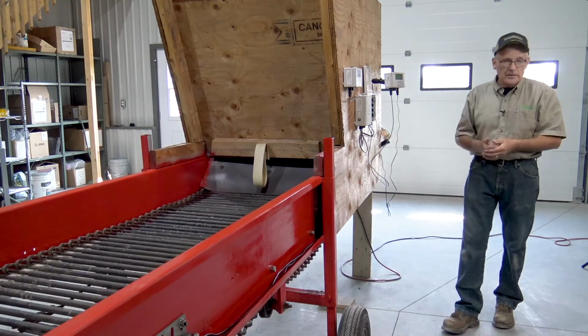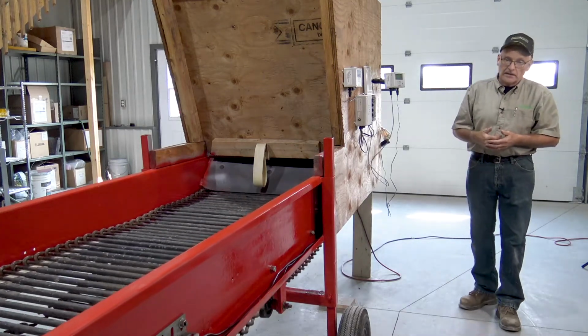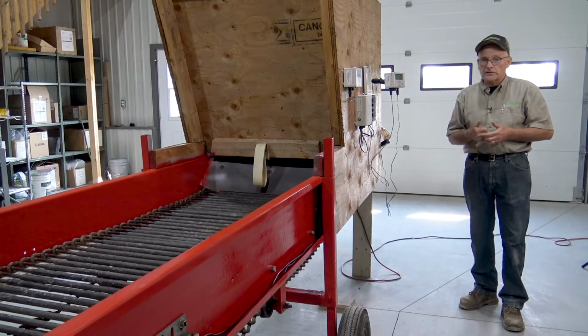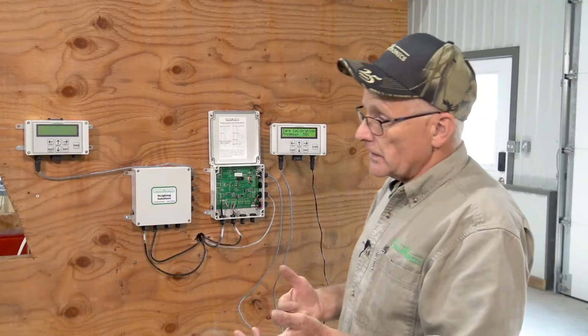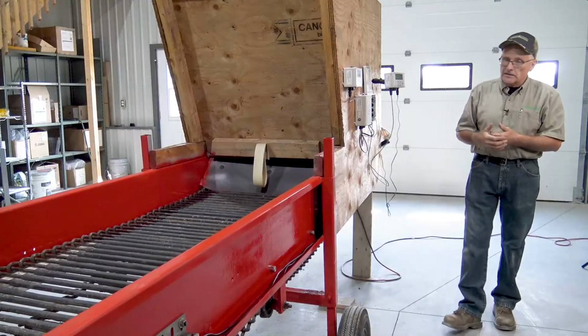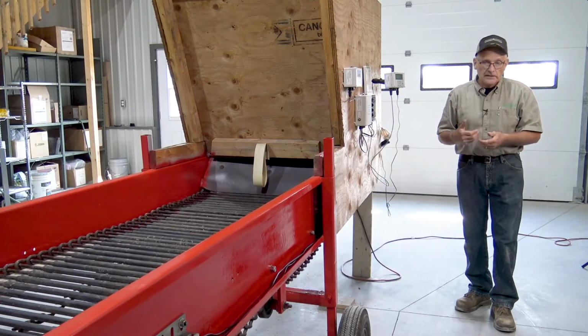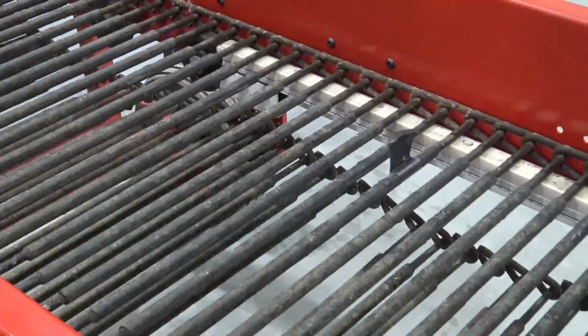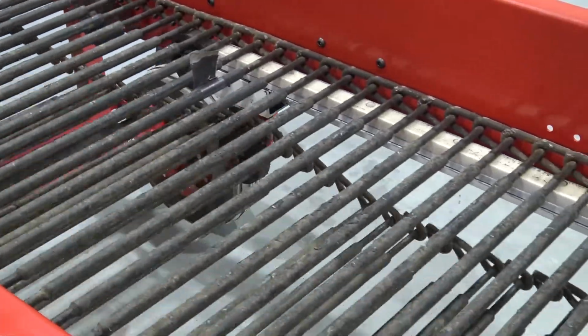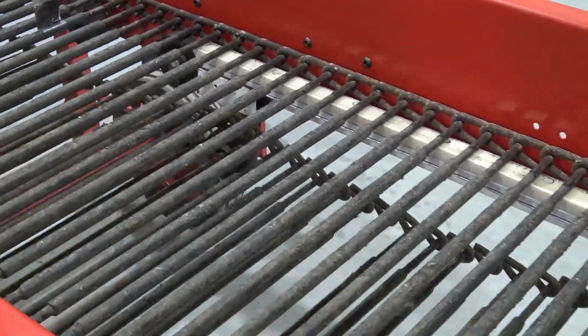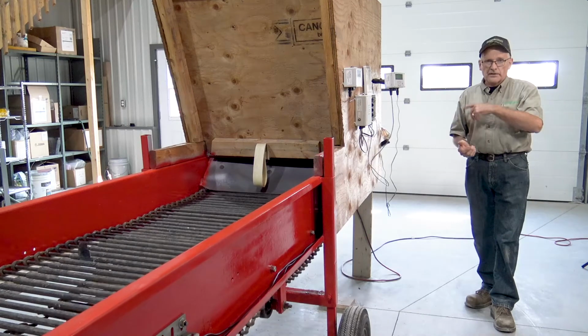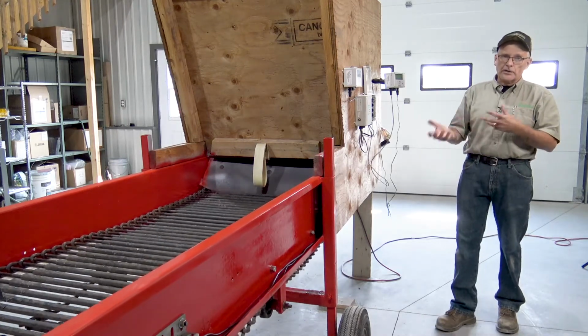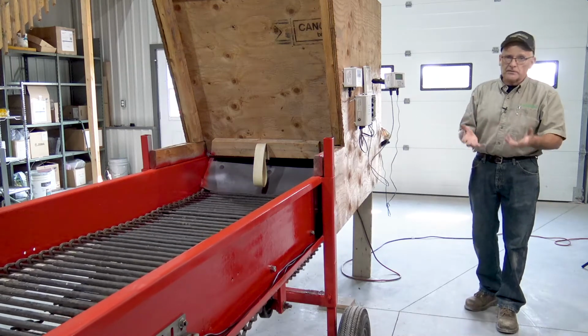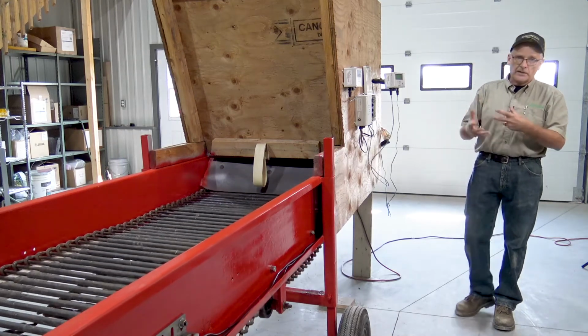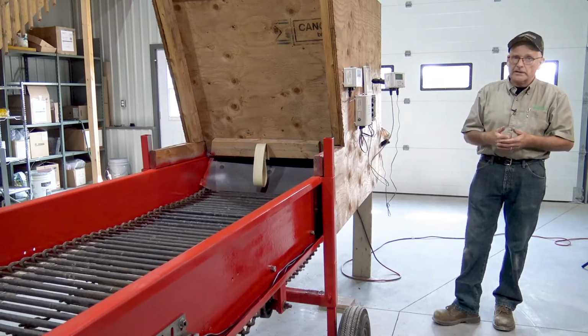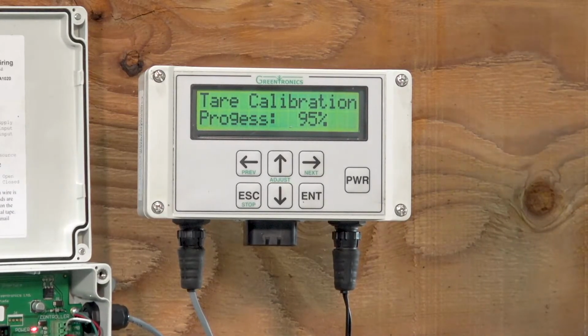So it's something that typically people do once a day, but again, as I said, if conditions change, you want to do that more than once a day. There's one other point I could make about the tare calibration, is that sometimes these machines sit outside, very cold. Sometimes we don't have a belted chain or a hook chain belt like this, but we have a solid rubber belt. That can get pretty stiff when it's cold. And so I would recommend that you let it run for a few minutes before you do that tare calibration. It just helps to become a little bit more flexible, and it will transmit its empty weight to the load cells better and more accurately. And there, we're almost at 100%.